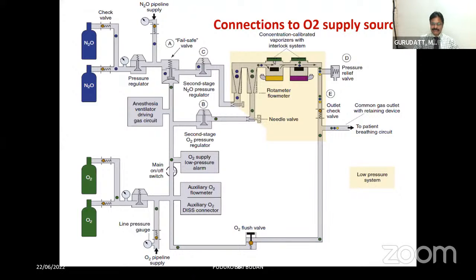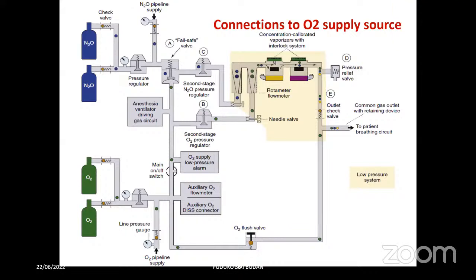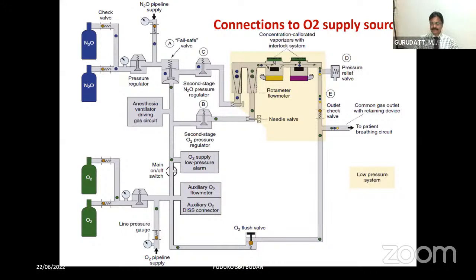Now coming to one of the other questions that will be asked of you: how many connections are there to the oxygen supply source? Many times you'll be asked this, so I just wanted to add it. The different connections of oxygen, either to the pipeline of oxygen or the cylinder of oxygen: one connection is directly to the flow meters, the second connection is to the fail-safe valve of nitrous oxide, and you have the third connection to the oxygen supply failure alarms.